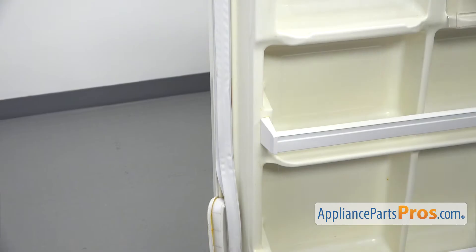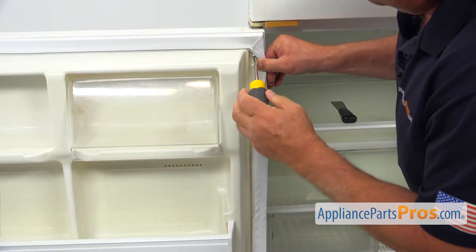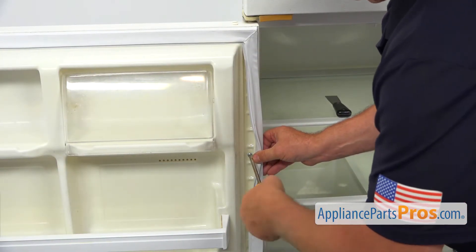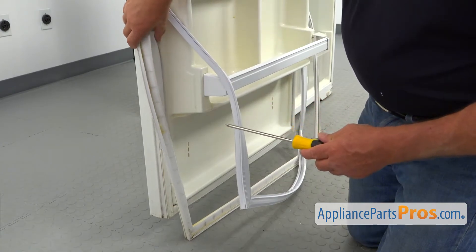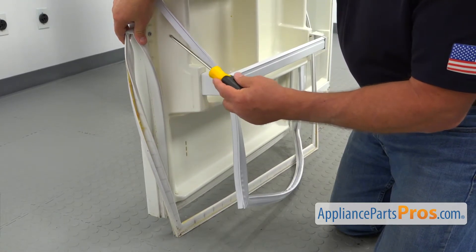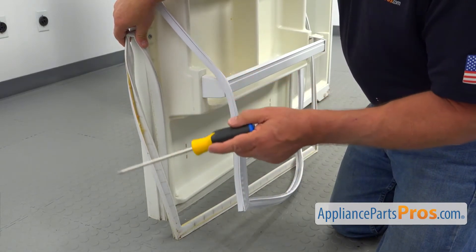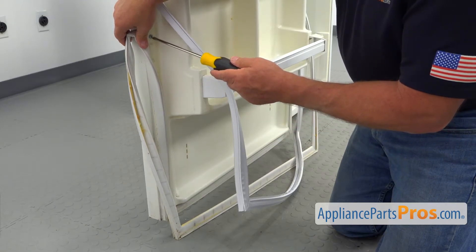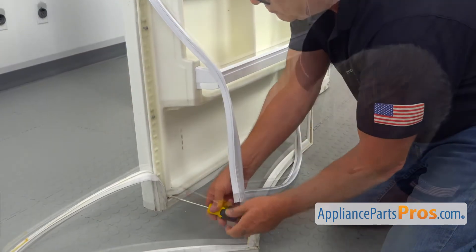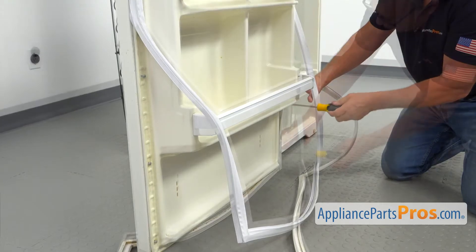Then we switch sides. Find the upper screw and loosen it, and one more. We're going to continue to loosen up the rest of the screws at the bottom half. In case you wonder why I'm doing that — why I'm not taking all the screws out and putting the gasket on at the same time — the answer is very simple. If I loosen up all the screws, I may move the lining, and in that case the lining would not be exactly in the same position when I put a new gasket on. And that would be a big problem.